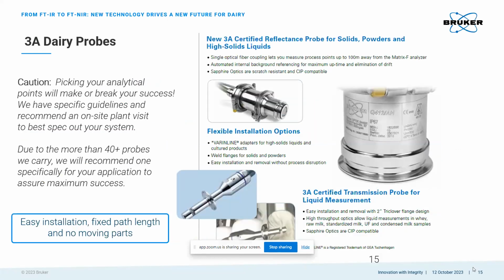Specifically for the dairy industry, we have 3A certified reflection probes and 3A transmission probes. Now, picking your probe location is what's either going to make or break your success, but we do have guidelines and, of course, always recommend an on-site visit to best spec out your system and make it successful. So just a little bit of background on the probes. The top probe, the Q413, does semi-solids and solids in reflectance, while the probe displayed at the bottom is going to be analyzing your liquids in transmission.